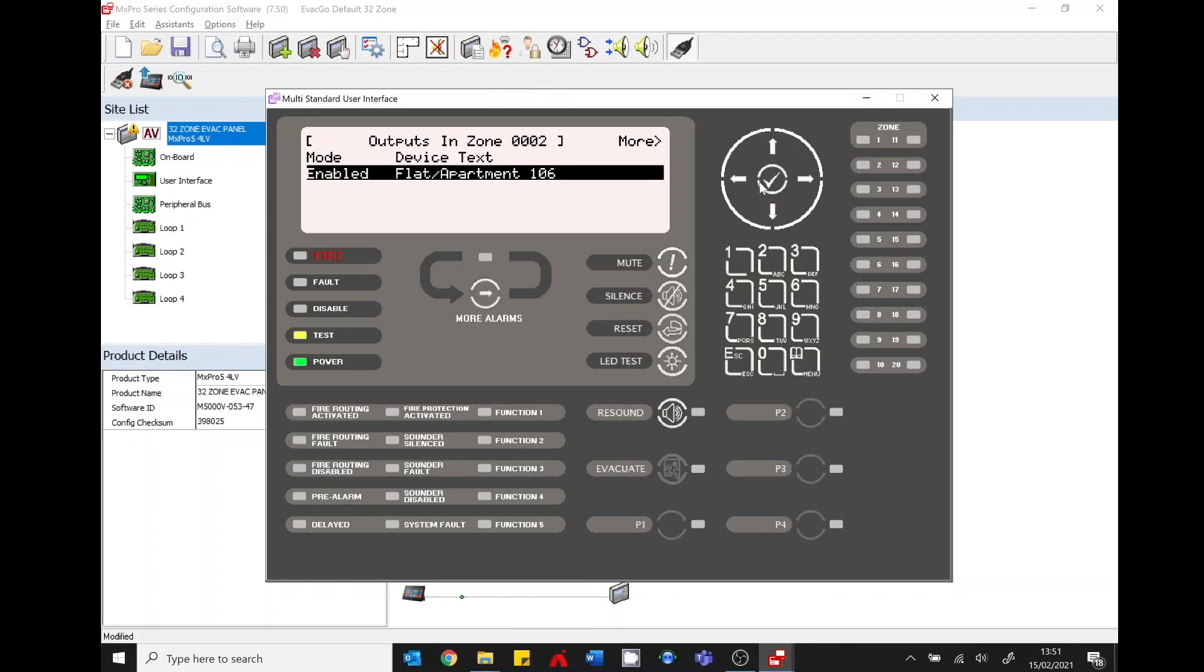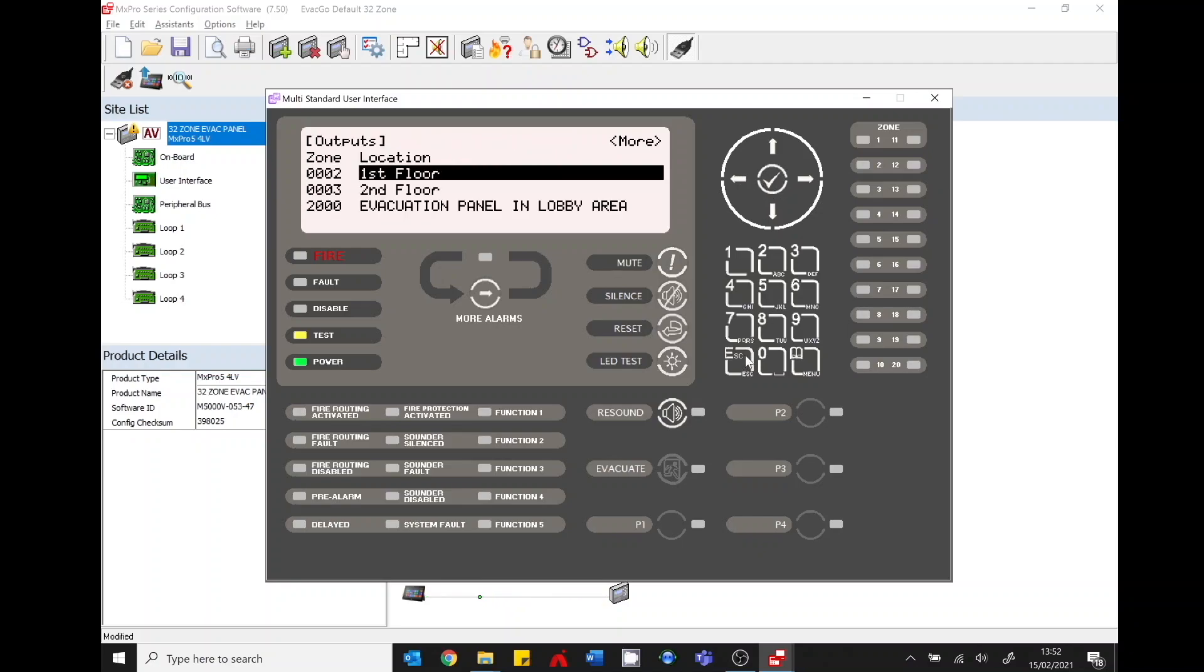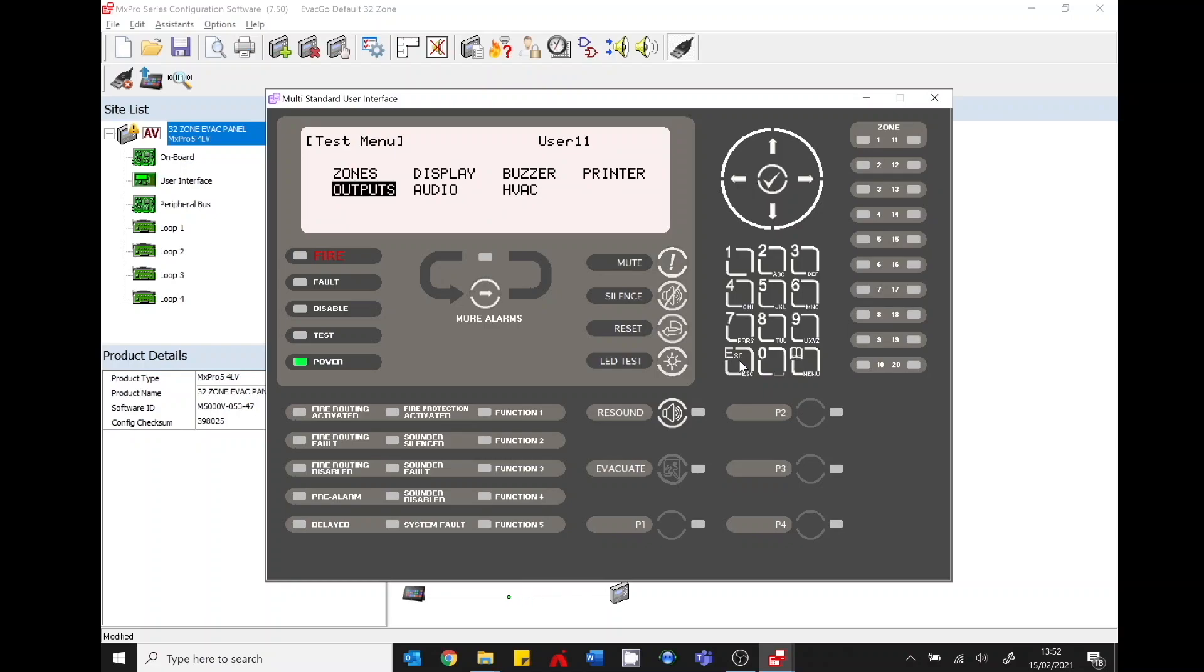Obviously if that sounder was to go into fault then it will give you a fault indication. Once you're happy with the test menu go through all. Every sounder should be tested. So go through every single evacuation zone testing each sounder and don't also forget to test the toggle switch for activation for the floor.